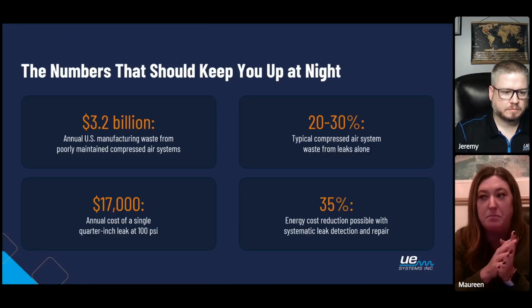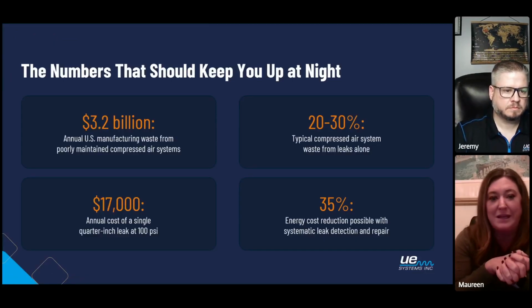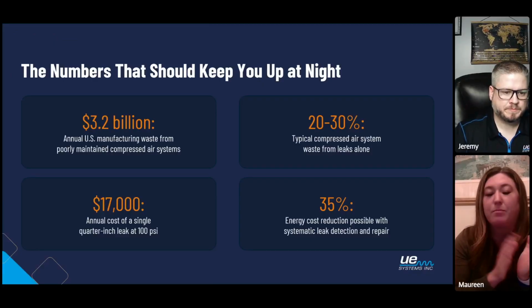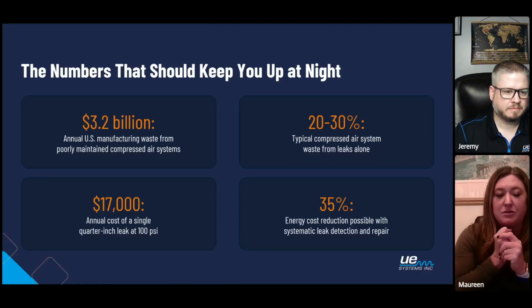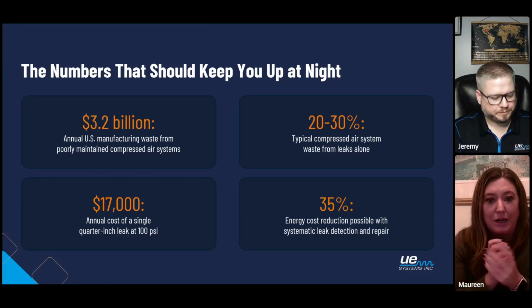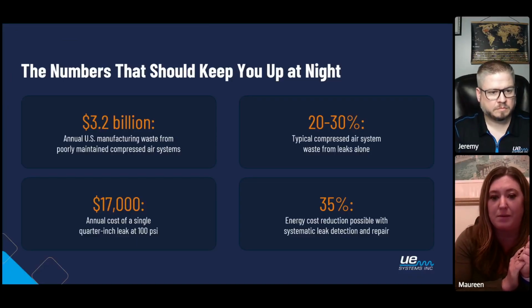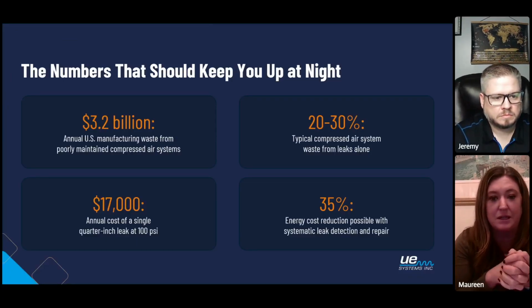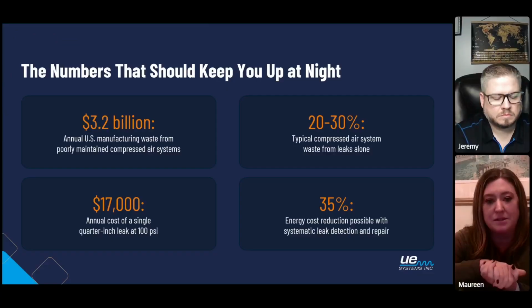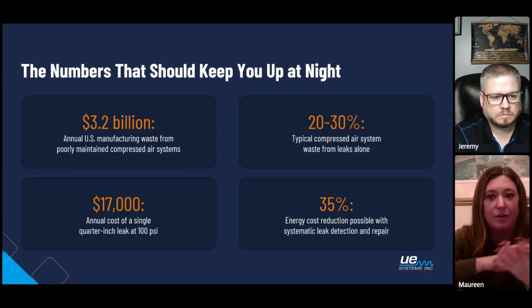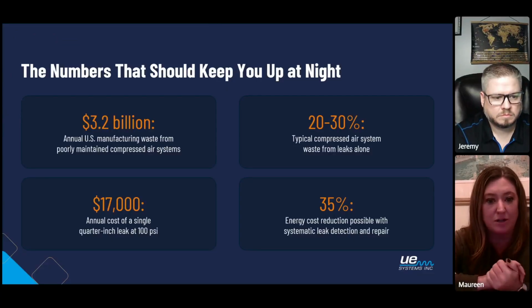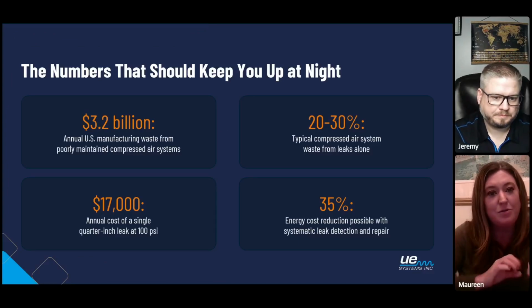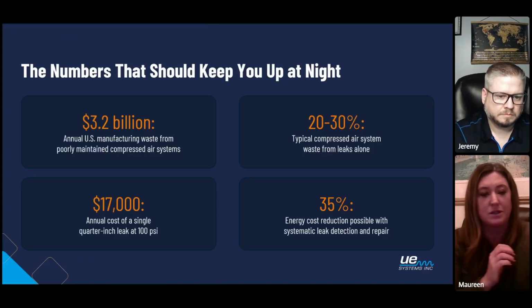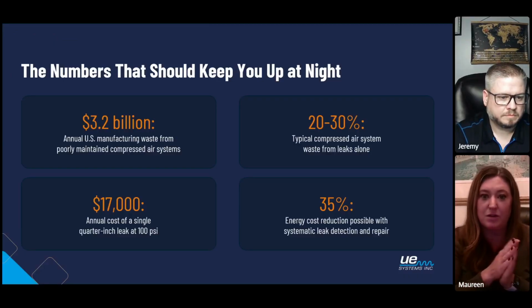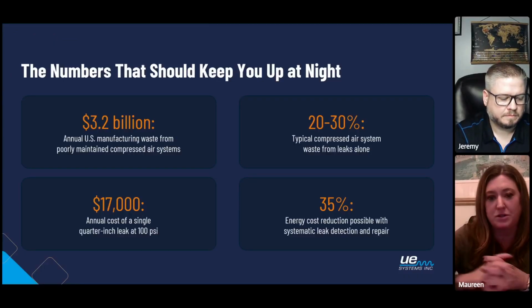3.2 billion is the annual waste from poorly manufactured, poorly maintained compressed air systems. We know that 20 to 30% of compressed air is wasted from leaks alone. And we know that the average cost of a compressed air leak is $17,000 annually. But we also know that we can reduce those issues by finding those leaks with ultrasound.